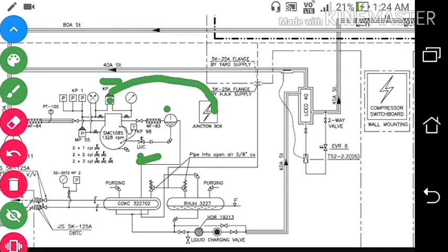Now this is the reciprocating compressor. In the air conditioning unit, we have a V type or W type compressor with almost 8 to 12 or even 16 cylinders. And in the compressor we also have an unloader valve. You can see these three pressure gauges. These are the three pressure sensors which will sense the pressure at the inlet to the compressor, and accordingly it will open and close the valves of the compressor unit.